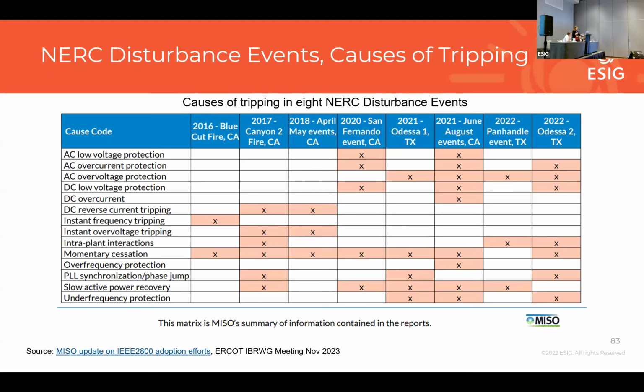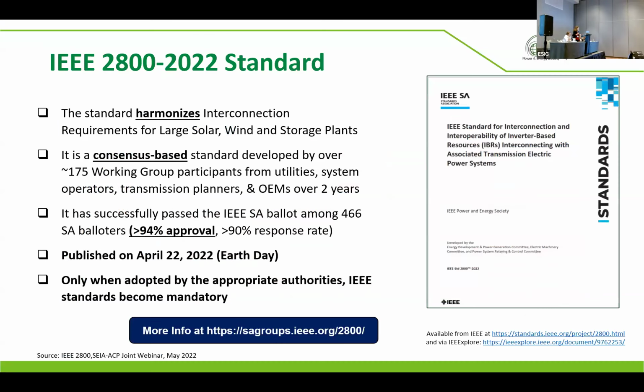And we need to do something with requirements for interconnection of inverter-based resources, but also with how we assess inverter-based resources during the interconnection process to make sure that this is not happening. And Cynthia has this zero event aspirational goal from the DOE roadmap, which I think can be achieved with good detailed interconnection requirements, but also a process for conformity assessment that these requirements are actually being met.